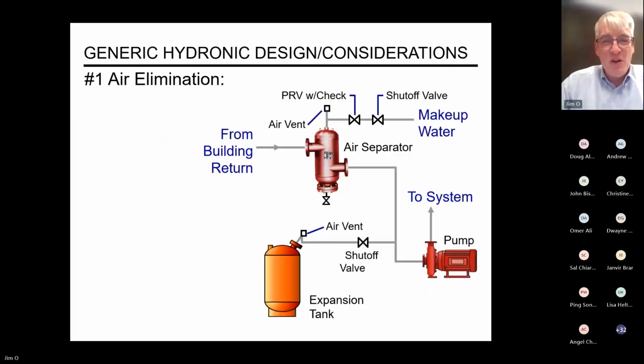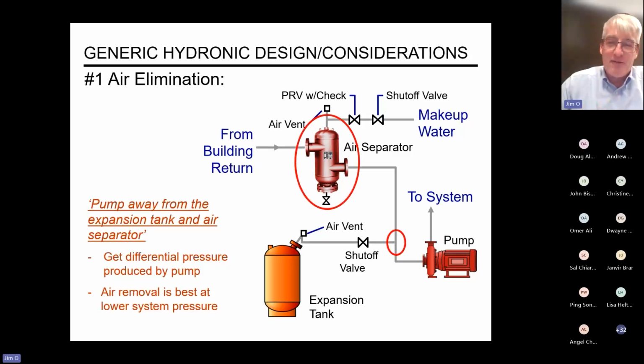All right. Another thing that's important with air elimination is to install an expansion tank and an air separator. Once again, this is a typical detail from seeing it over the years. I'm not going to go into the function of what the air separator does, the expansion tank, makeup water, et cetera. And then I just have to chuckle to myself at the term that I have here in italics: pump away from the expansion tank and the air separator.